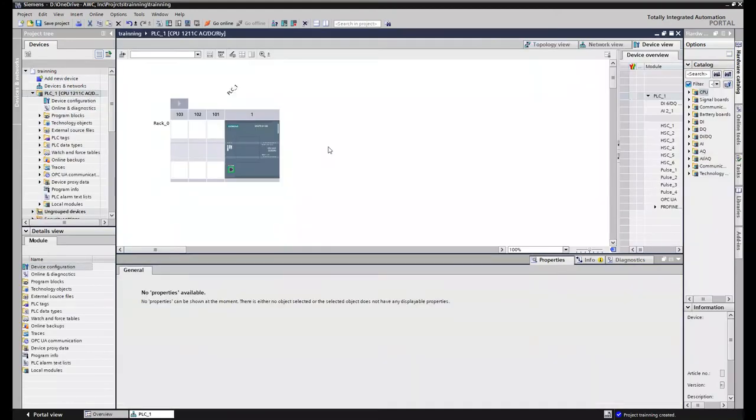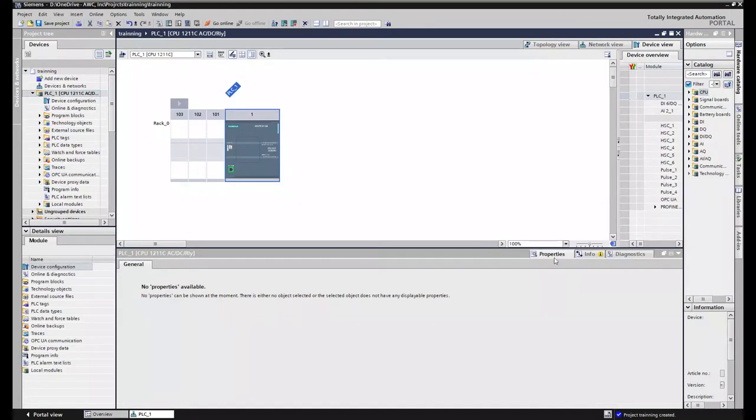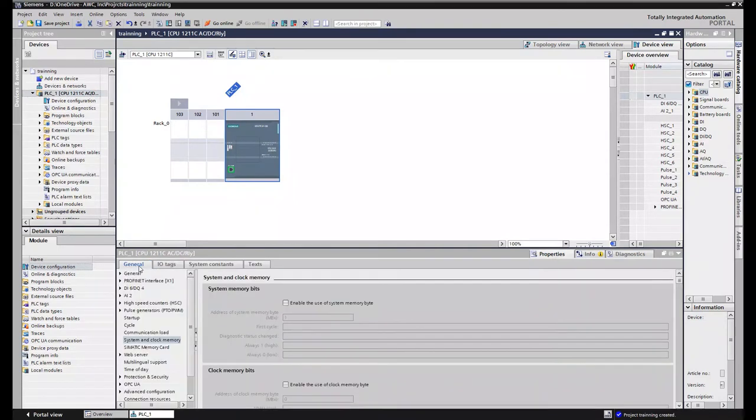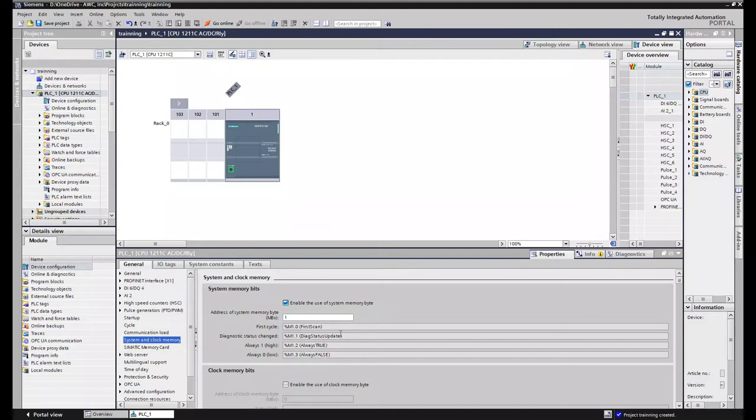Now that the PLC has been added you can single click on the PLC, go to properties. And then underneath the generals tab you can scroll down to system and clock memory. And then we can enable it by checking this box. By default it'll be m1.0 through 1.3 which includes the first scan bit, the diagnostic status update, your always true bit and always false bit.